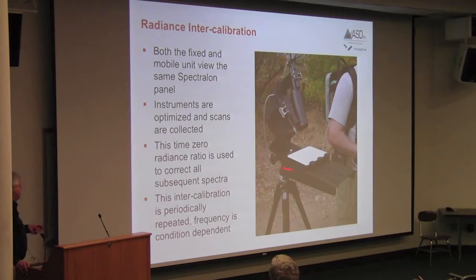We call this the time zero radiance ratio. What we found is that you do this when you start up at the beginning of the day, but probably once every 20 minutes or half an hour, it's not a bad idea to go back and do this every once in a while if you want everything to be as tight as possible.